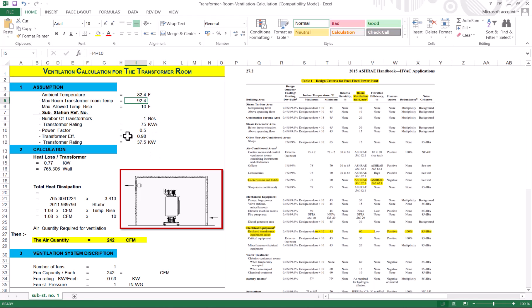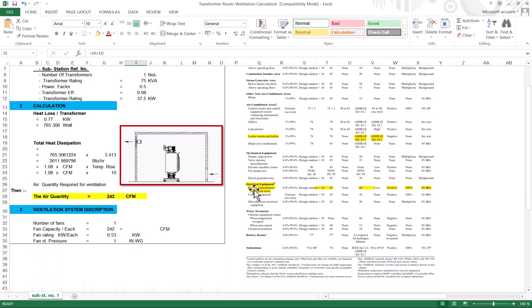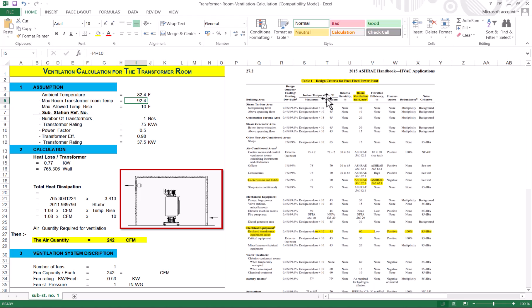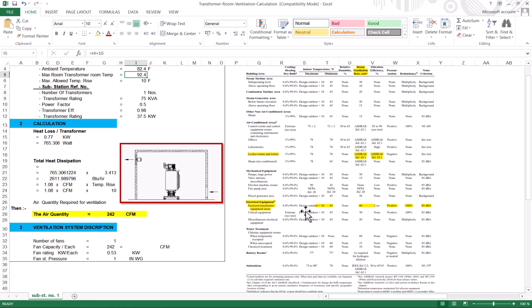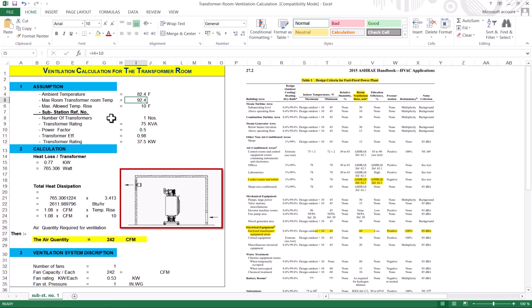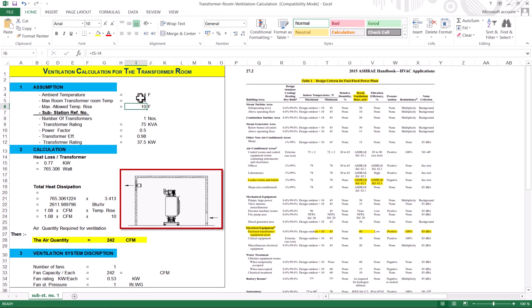Where do we get this criterion? In the ASHRAE 2015 Handbook design criteria, under electrical equipment in enclosed transformer areas, it specifies that the indoor maximum temperature is the design outdoor temperature plus 10°F. This is the maximum indoor temperature you want to maintain in the transformer room. Also, 45°F is the minimum temperature for the transformer — you cannot let the room temperature drop below 45°F.